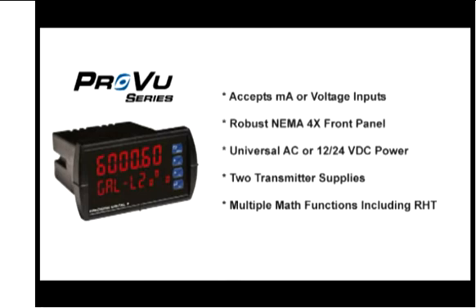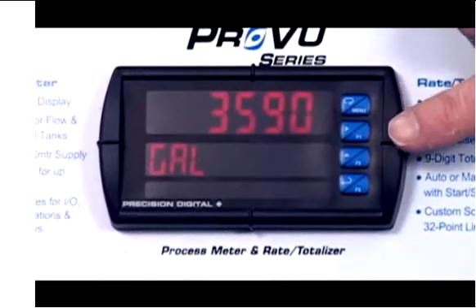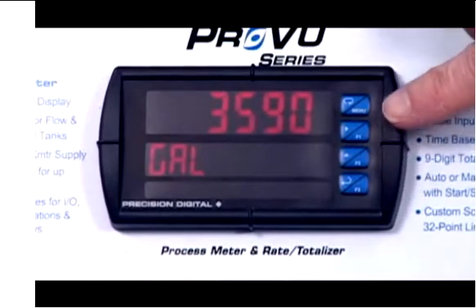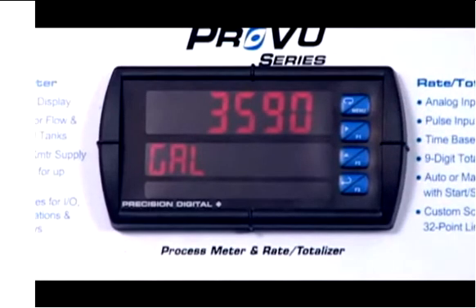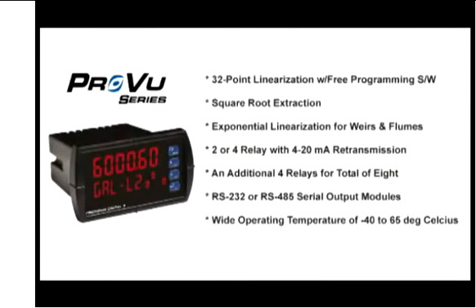The ProVu also has math functions for flow and round horizontal tanks. A very unique feature is these three function keys you see on the front panel, and those can be used for things like resetting the alarms. There's also the ability to do 32 points of linearization, and we have a computer-based program to make inputting those points very simple.